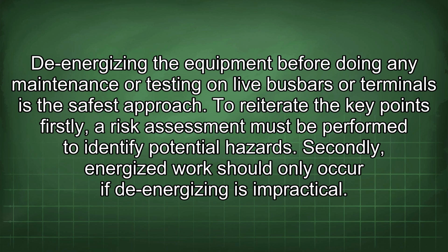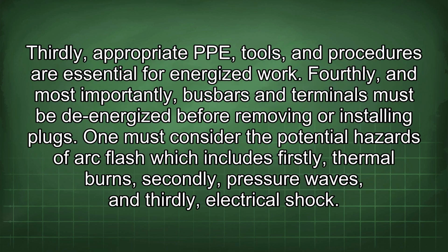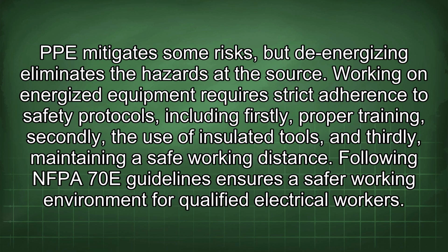To reiterate the key points, firstly, a risk assessment must be performed to identify potential hazards. Secondly, energized work should only occur if de-energizing is impractical. Thirdly, appropriate PPE, tools and procedures are essential for energized work. Fourthly, and most importantly, busbars and terminals must be de-energized before removing or installing plugs. One must consider the potential hazards of arc flash, which includes firstly, thermal burns, secondly, pressure waves, and thirdly, electrical shock. PPE mitigates some risks, but de-energizing eliminates the hazards at the source.